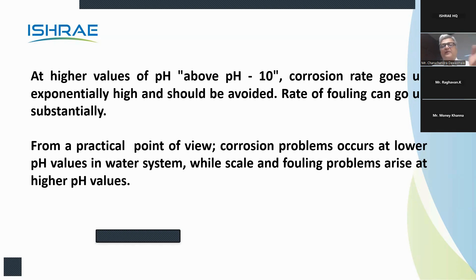From the practical point of view, corrosion problems occur at lower pH of the system, 7 and below, while scale and fouling problems arise at higher pH values, between 7 and 14. These are the pH ranges which are connected with the fouling, corrosion or scaling issues.